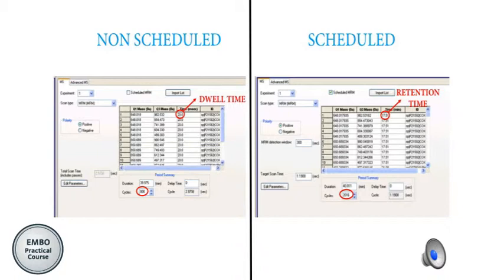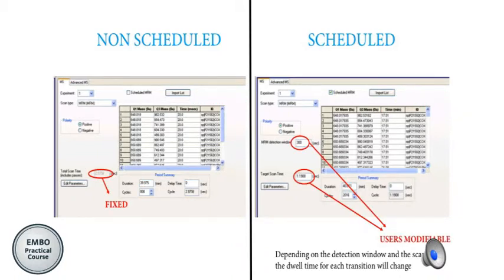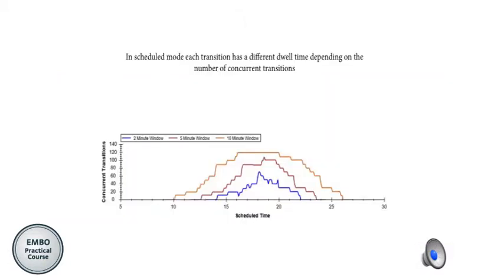In the case of scheduled MRM, instead of dwell time we enter the retention time and fix the scan time — for example a target cycle time of 1.2 seconds. At each moment in the chromatography the software calculates how many transitions are co-eluting and divides the available time among those transitions, so the dwell time changes from transition to transition.